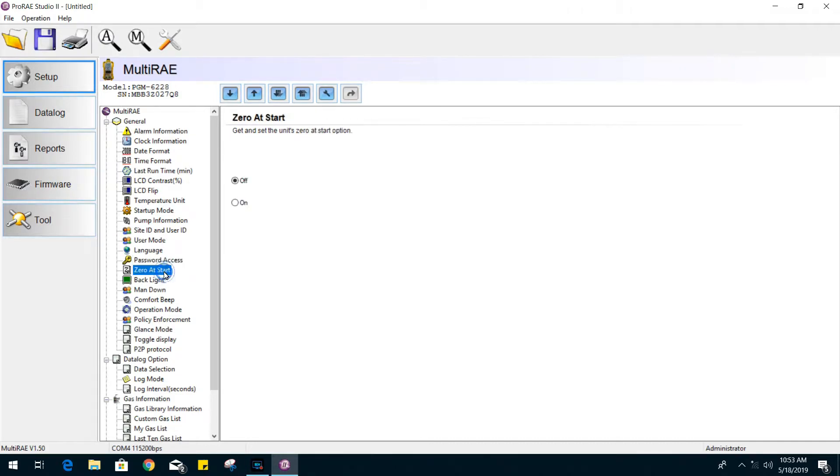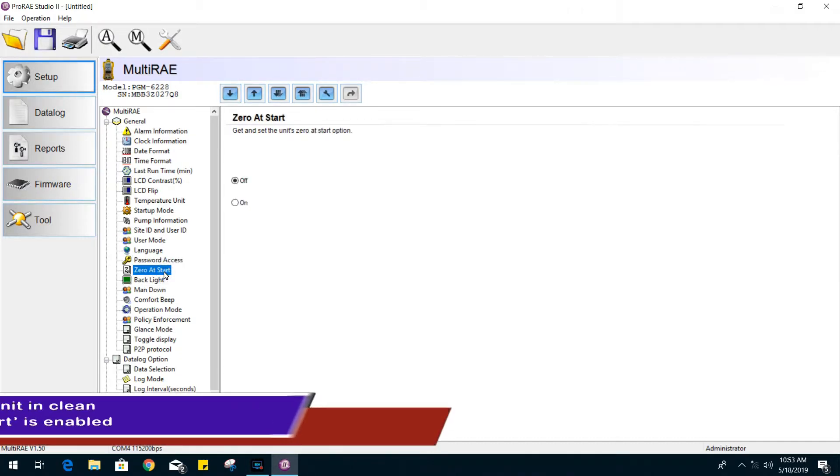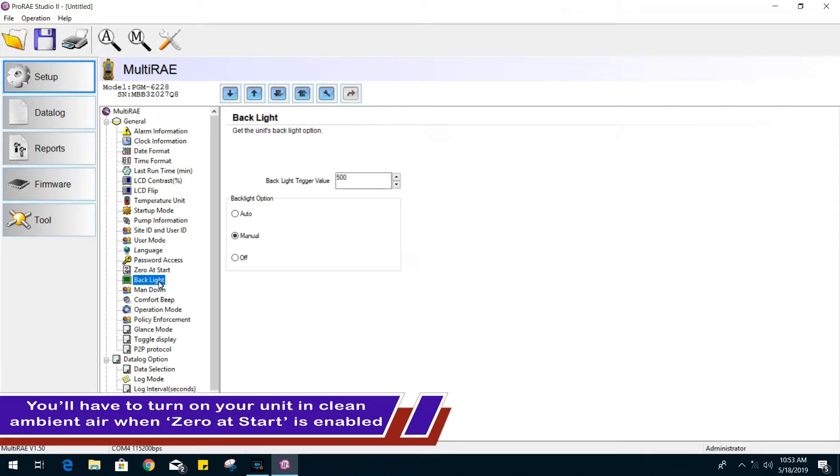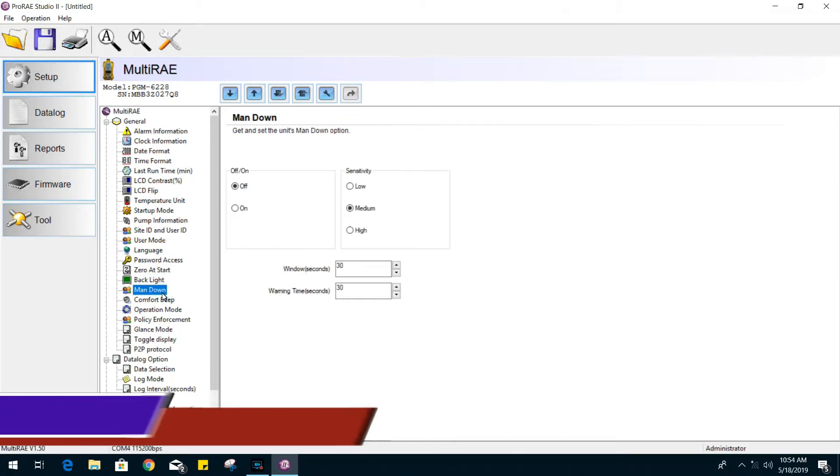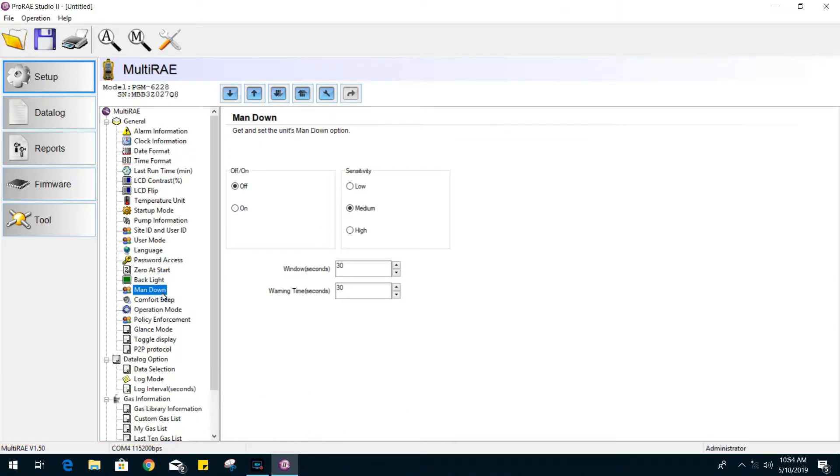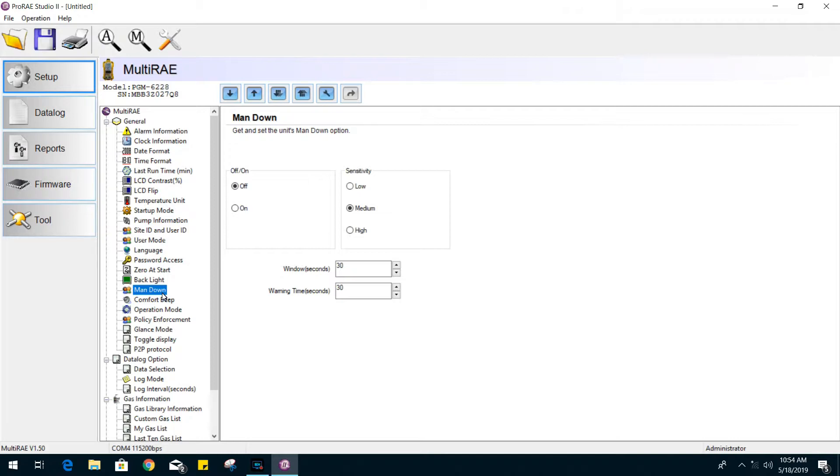Zero at start. The backlight option as well. The man down feature when enabled will detect any rash movements with its built-in accelerometer and notify the user when he's down. If you don't acknowledge the man down in a number of seconds, it will go into alarm and send a signal if you are set up in a network.